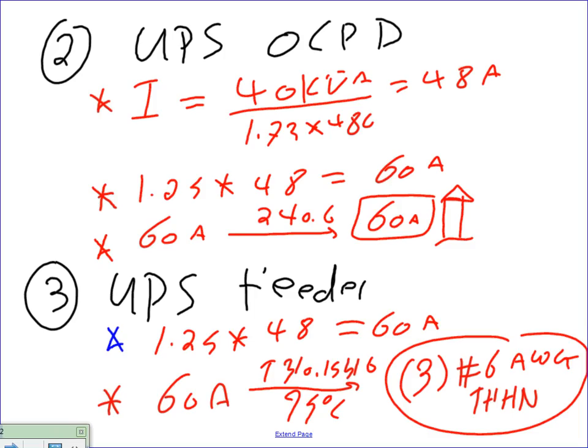That's the process that we start. When we know the material, if we discover the manufacturer of this product really wants us to put 70 here, we go ahead and put 70. Manufacturer's rule. Or they want the feeder to be number 1 instead of number 6, you go there and put number 1. Most of the time, guys, they're going to follow these rules, so you're not going to be off.